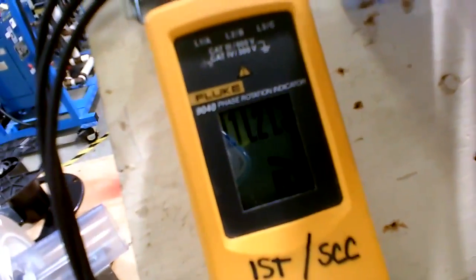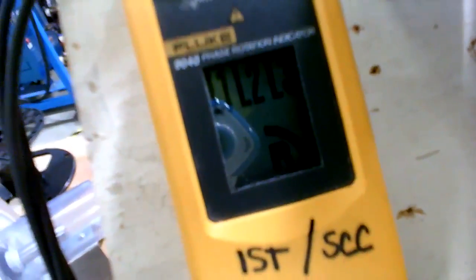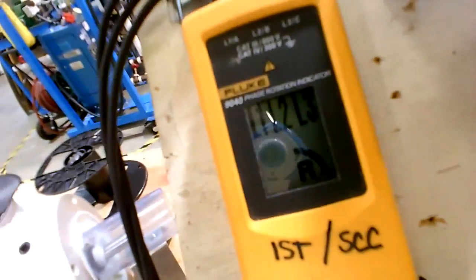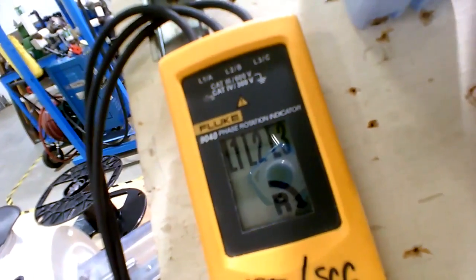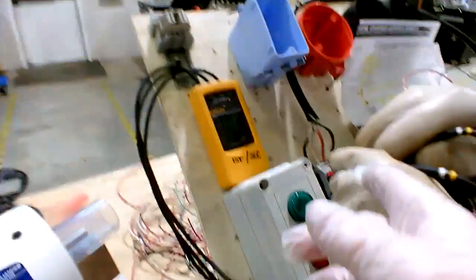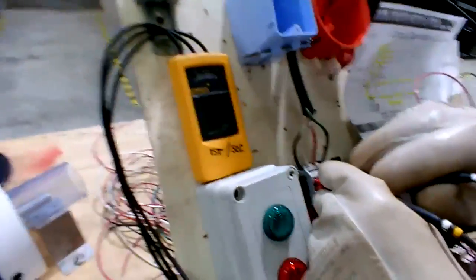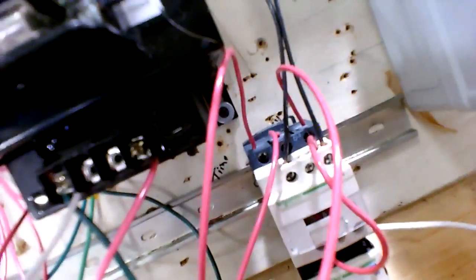So what he's done is he's put those 3 leads in there, and you need to look up here to see what you might be missing. Now, it's telling you that the shaft will go clockwise. You see that arrow? The shaft's going to go clockwise if you keep that same phase rotation all the way through. So let's follow it through. Take the leads off. If you keep the 1, 2, 3 sequence from that terminal strip all the way through the starter, and you keep that sequence from the bottom of the starter all the way to the motor, it goes clockwise.